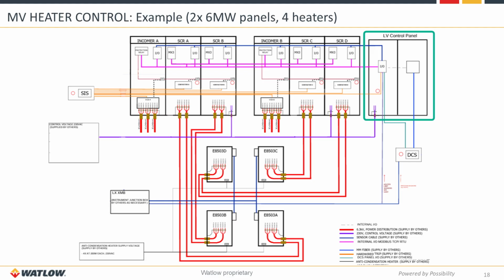It also has redundancy built into the low voltage control panel. So there's a standalone low voltage control panel for this particular system that talks to and integrates with the first group of panels and the second group of panels through the I/O. This is hardwired I/O and Modbus communications to each one of those. The low voltage panel then talks to the DCS within the system to ensure that it's getting the proper signals, not only the duty cycle signals, but status signals, command signals, things like that, that will operate the overall system.